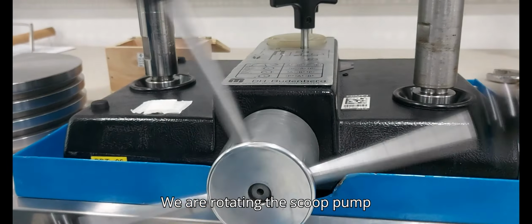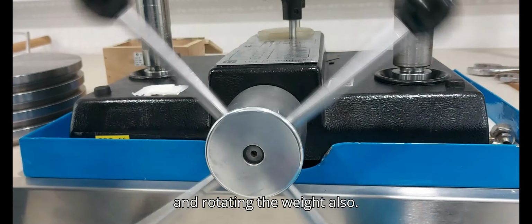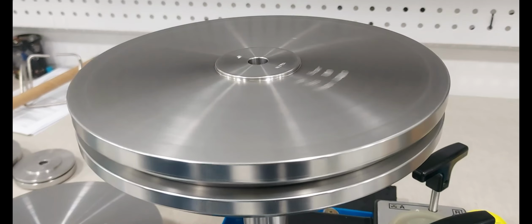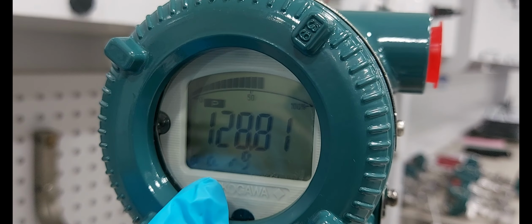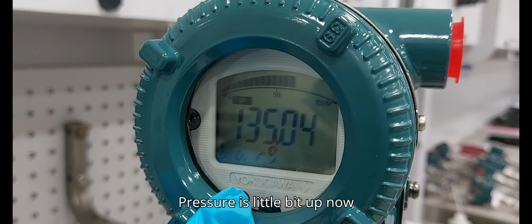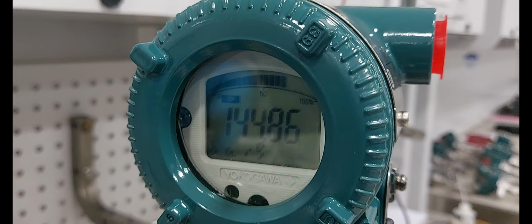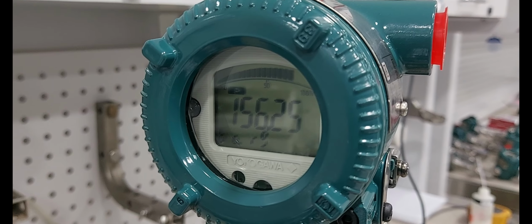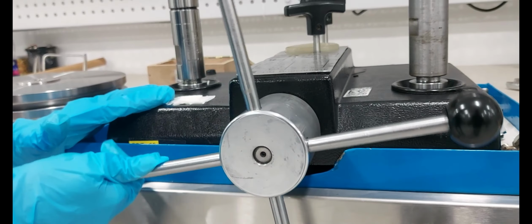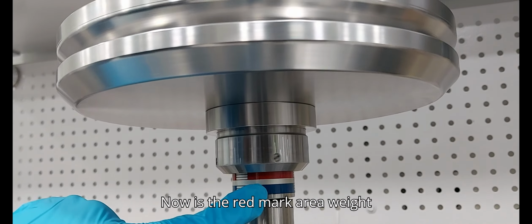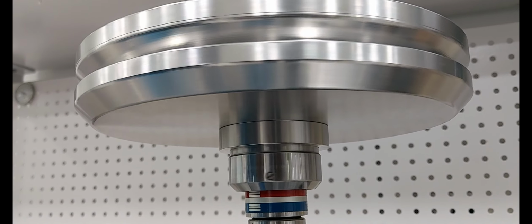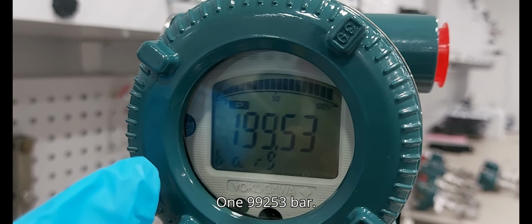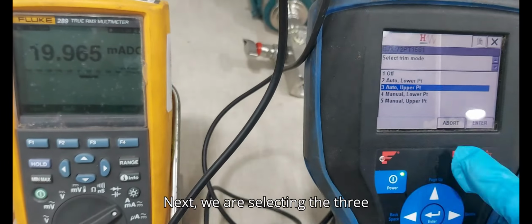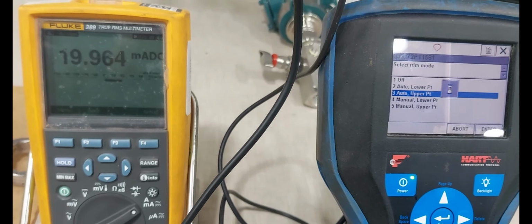We are rotating the screw pump and rotating the weight also. Pressure is a little bit up. Now 130 bar something. Now it is in the red mark area, weight set 199.53 bar. Next we are selecting the 3 upper range trim.